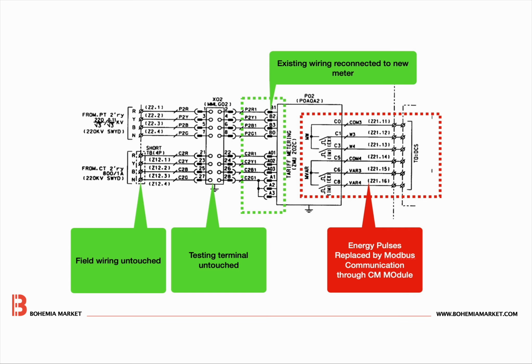At the same time, most primary equipment can remain unchanged. Current transformers and voltage transformers are still suitable and continue to provide correct signals. The issue is not the measurement itself, but how the data is communicated.